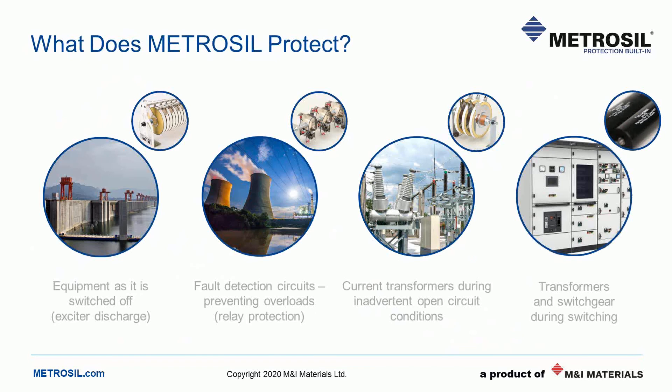What does a Metrosil protect? Historically we have four main applications, though we're certainly not limited to those. The first is generator de-excitation, where energy stored in electromagnetic field windings needs to be discharged safely and quickly. Second, relay protection, used across high impedance relays or REF — restricted earth fault — schemes. Third, current transformer protection, where a secondary winding must be protected from an open circuit. And fourth, switchgear protection. These electrical network applications have IEEE recommended practices and regulations which specify the use of varistors.